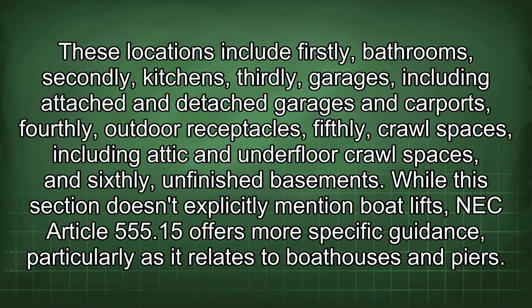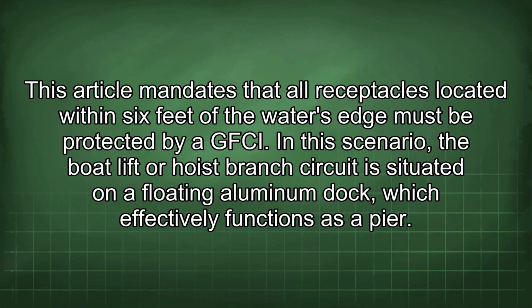While this section doesn't explicitly mention boat lifts, NEC Article 555.15 offers more specific guidance, particularly as it relates to boathouses and piers. This article mandates that all receptacles located within 6 feet of the water's edge must be protected by a GFCI.